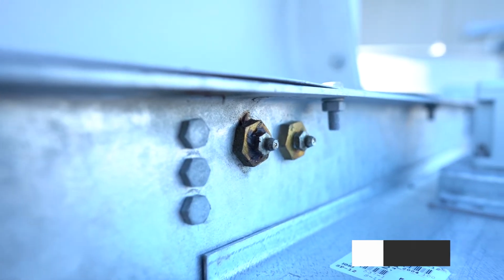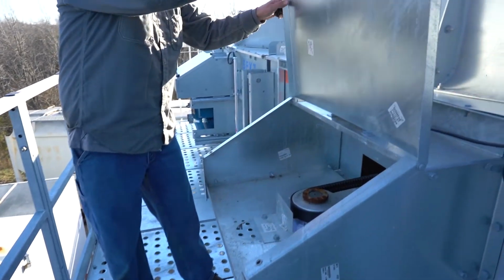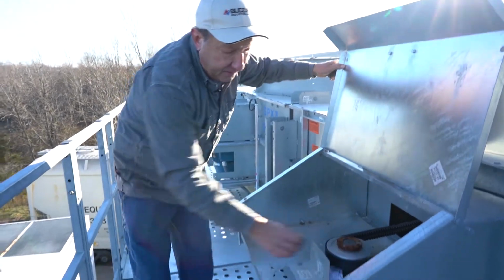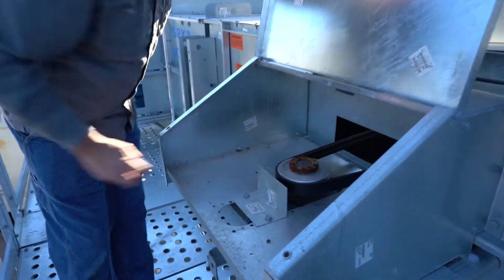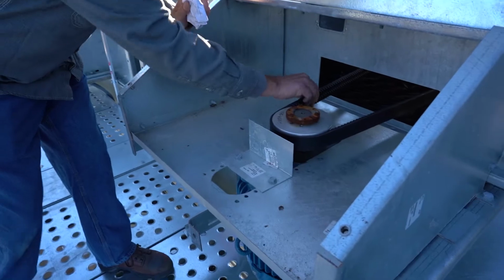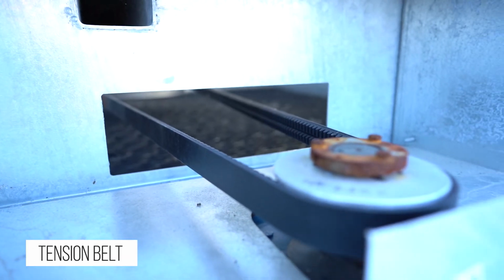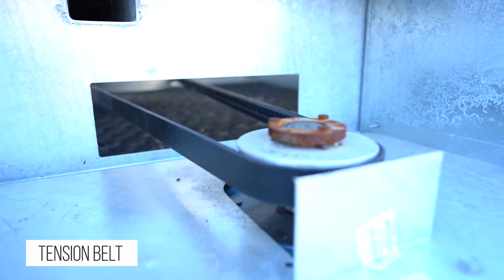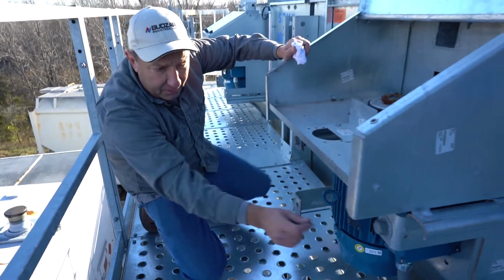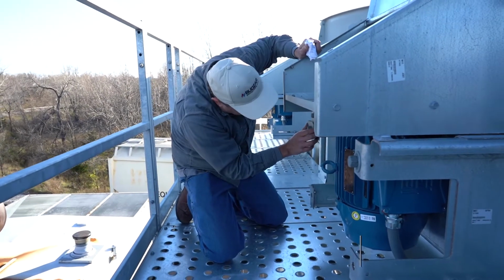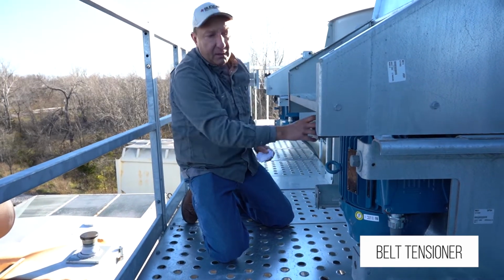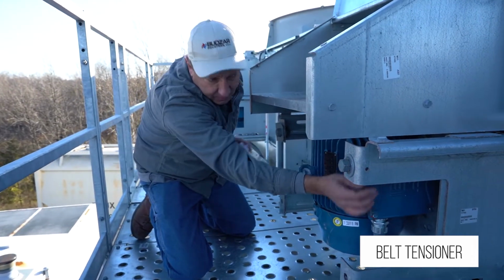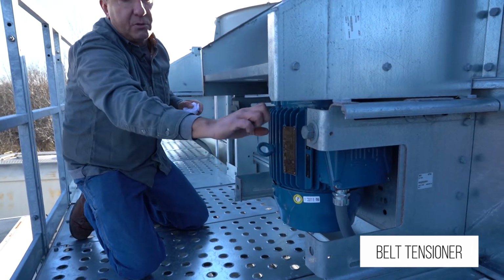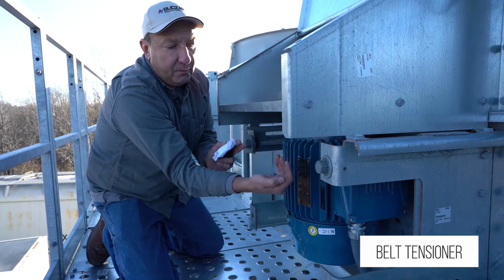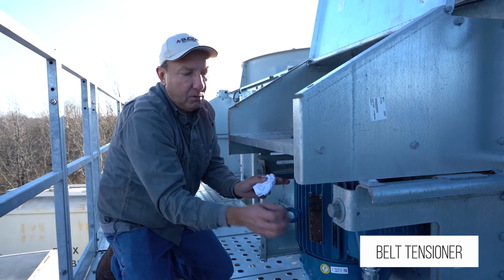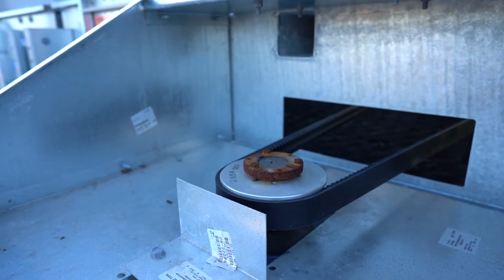Then, if we lift this cover, this is where the tension is. This is where we can adjust the tension of the belts. Right now I have these set right to the factory specs, and then down below you have the pulley systems where you adjust the tension. It's on a screw to where you could basically pull the motor back farther and increase tension, or push the motor forward and decrease tension.